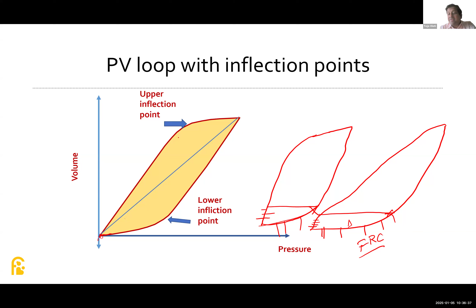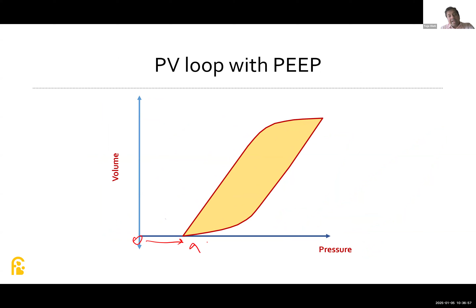What is the upper inflection point? Here, if it is too far, that means maybe we are giving excessive peak inspiratory pressure for that baby. Once you add the PEEP into the PV loop, it will start from the baseline, from a distance from the 0 point on the x-axis. This is how it will appear if you are adding PEEP to the baby. When you are using very excessive PIP, how do we know it from a PV loop?